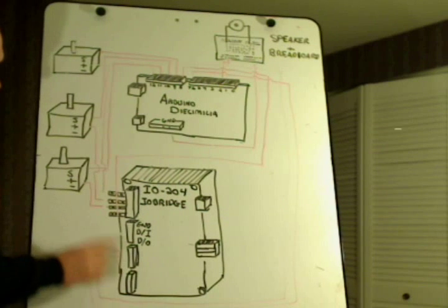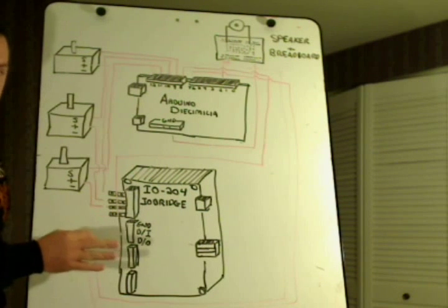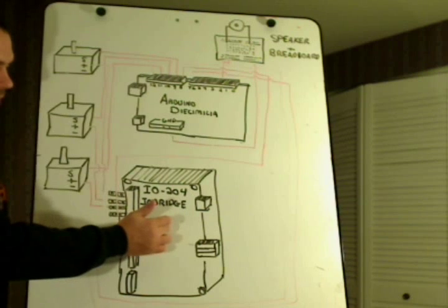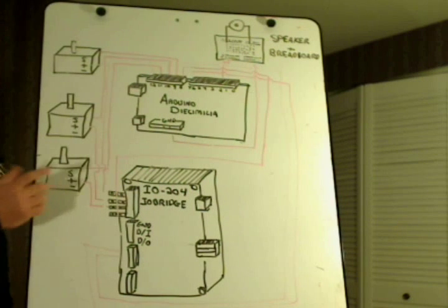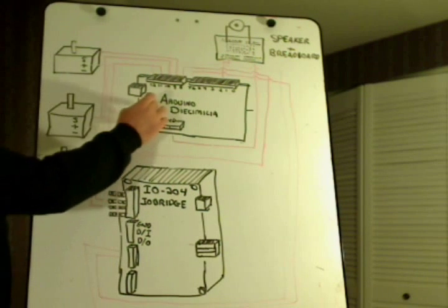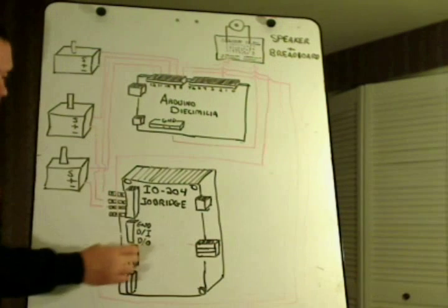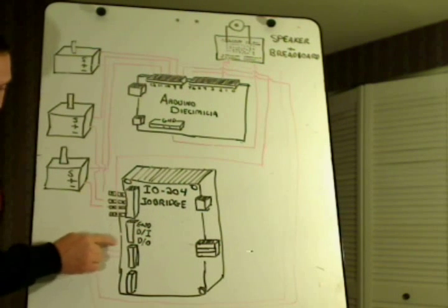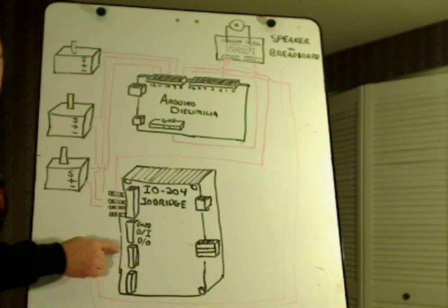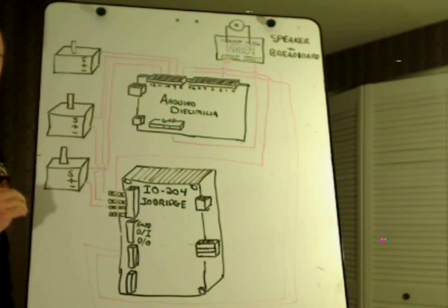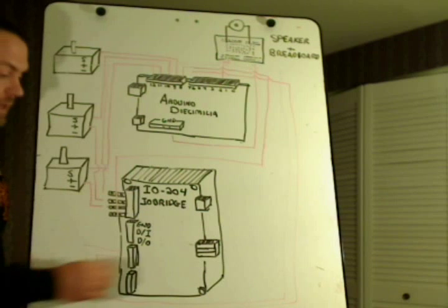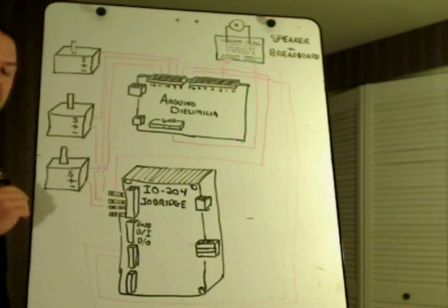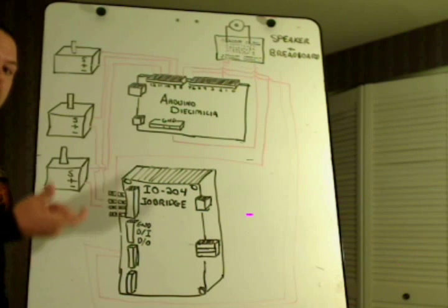Now I want to call your attention to really the three major lines that make the I.O. bridge and the Arduino talk together. First of all the Arduino has an output pin into the I.O. bridge on channel three telling the I.O. bridge it's ready to receive commands. So it will send pin high to the I.O. bridge module telling it that it's ready to receive commands, and I'll see that update on my web page.